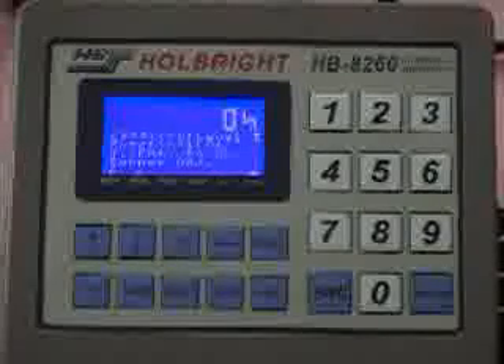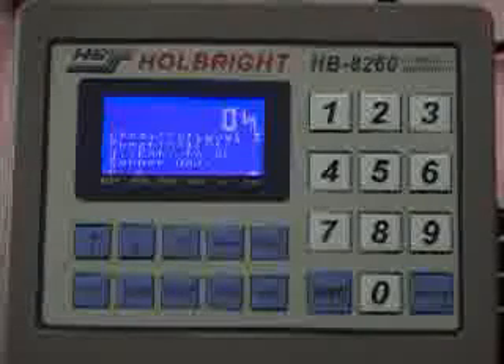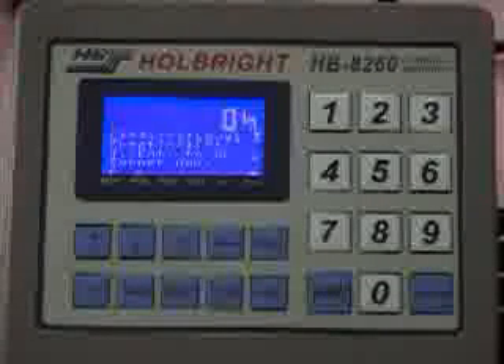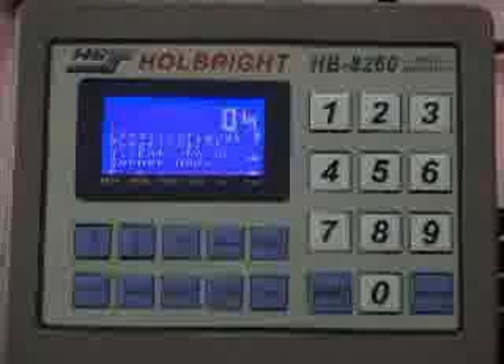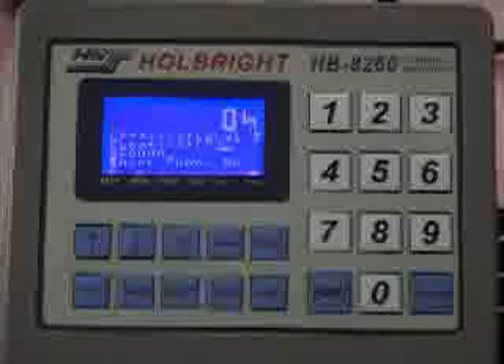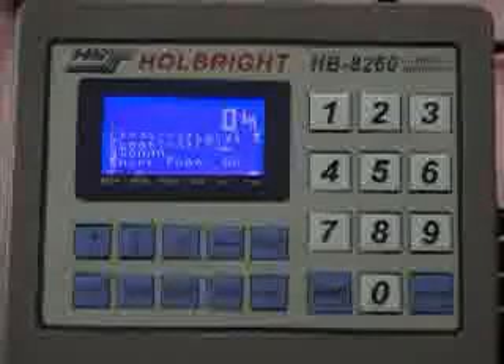The HB-8260 adjusts the system's corner calibration automatically. It requires users to do zero adjustment and span calibration right after the corner calibration. Press Enter to do the zero adjustment. Next step: span calibration.